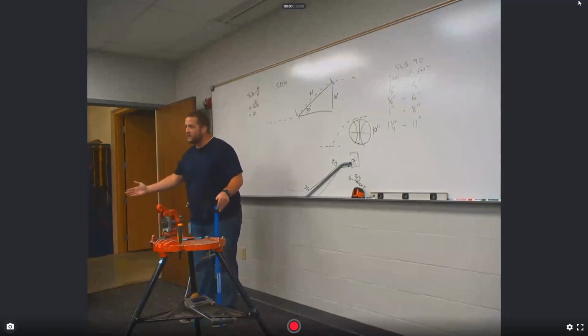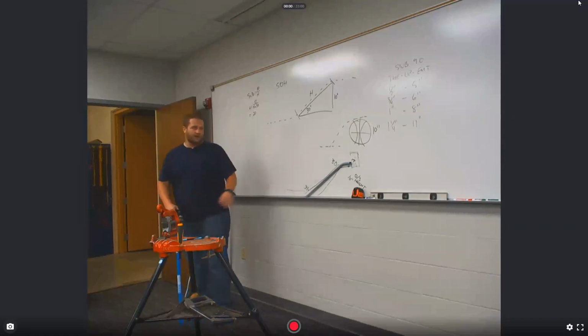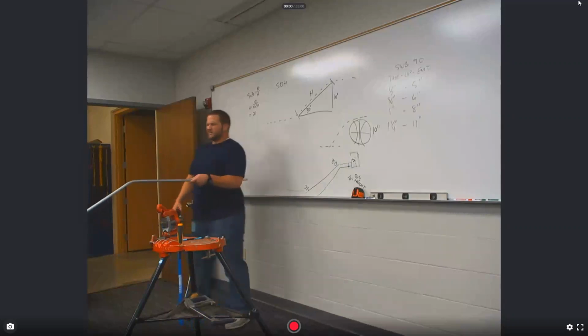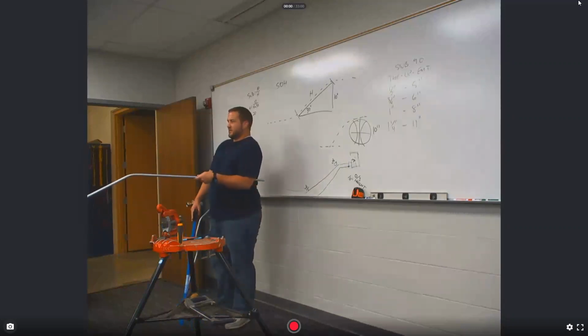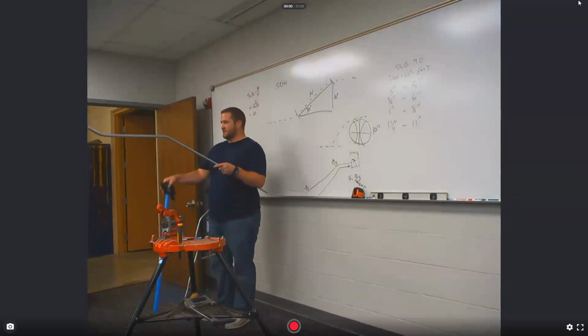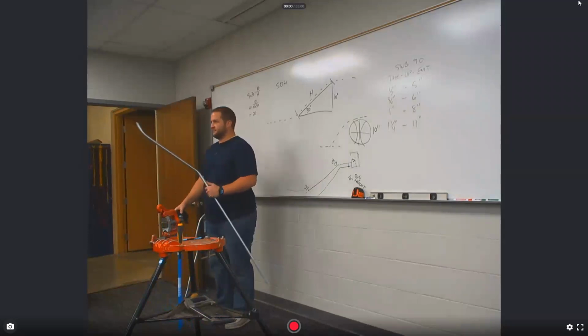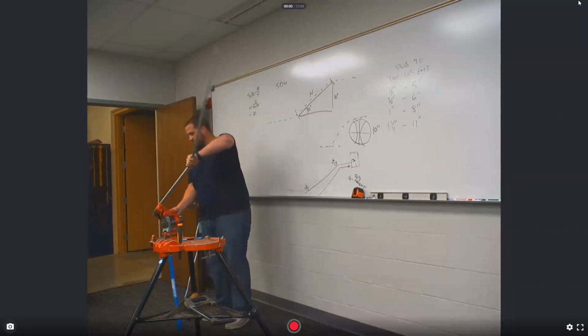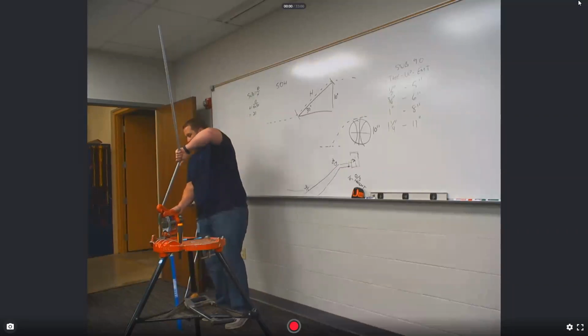Your marks are 10 inches apart, like you're doing it properly. Making it look good just comes with practice. But this is what a dog leg looks like. You see it? So that's not lining up with the bender. Now you asked, can you fix that? Sometimes you can.